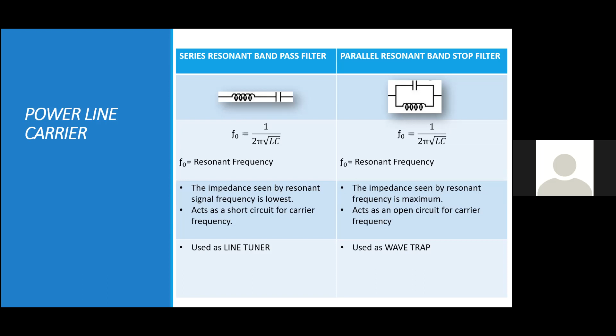So there are a few considerations we should be considering while using power line carrier. The first thing is there should be no reflected power. What do I mean by that? We get reflected power when the impedance of the transmission line does not match with the impedance of the coax cable used to connect the line tuner to the relay. So the first thing you need to do while commissioning a power line carrier circuit is match the impedance with the impedance matching transformer, which is the part of the line tuner circuit.